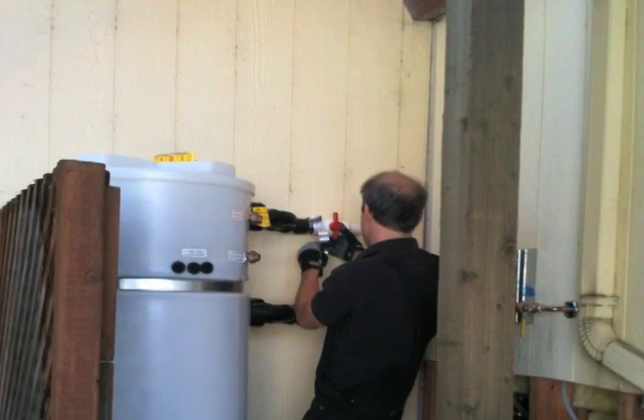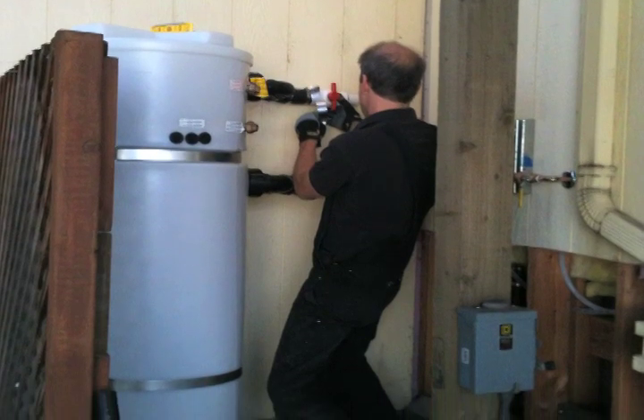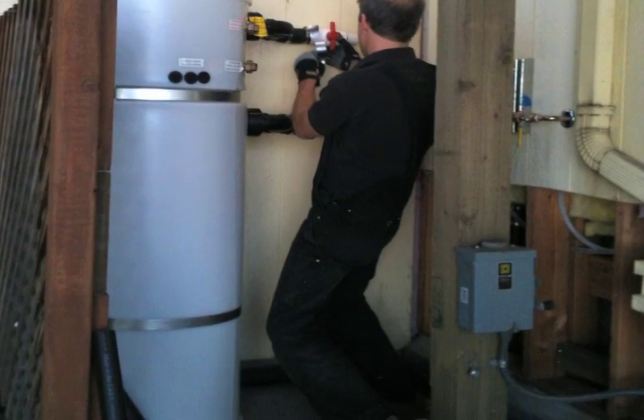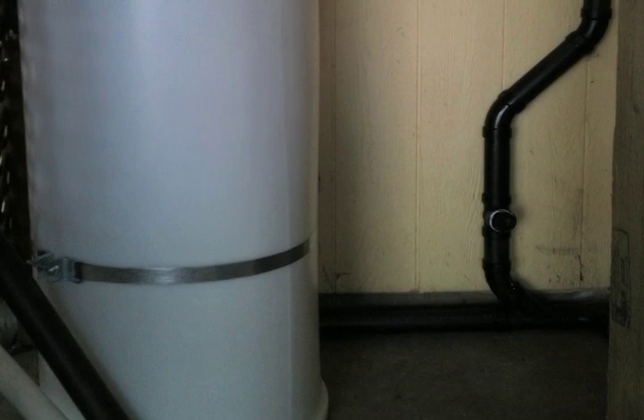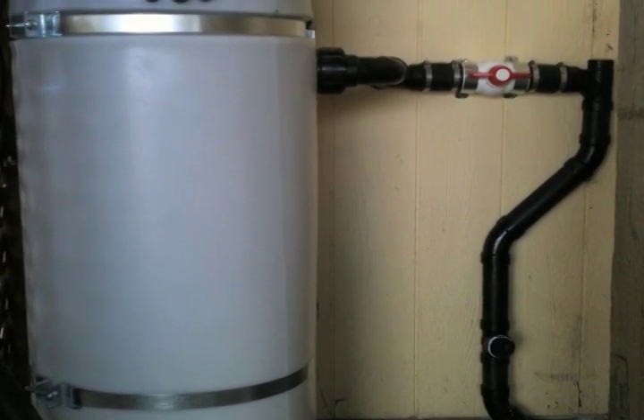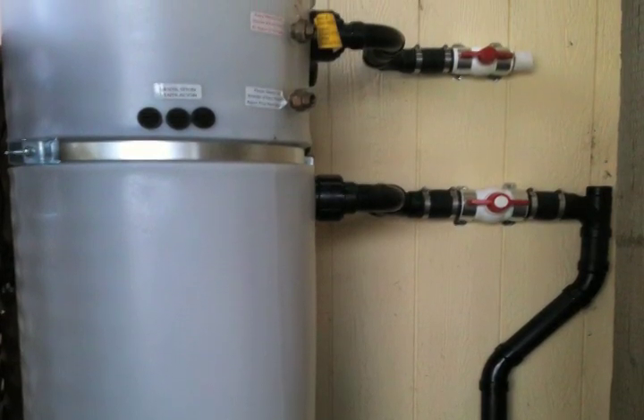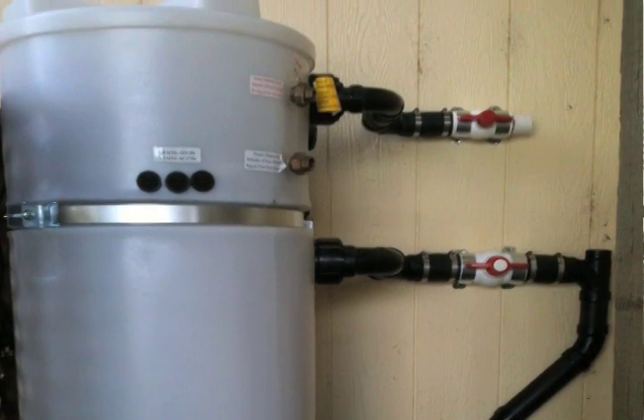For this project, we selected a BRAC filtration system for use. This is one unit that includes a pump, a filter, and a storage tank all together. We like this system because in the state of Oregon it is already approved for use. It also has a backflow that keeps gray water separate from city water, which is a very important aspect for any gray water recycle system. And finally, it has an automated chlorination system. This kills off pathogens and allows our gray water to be stored for longer amounts of time.